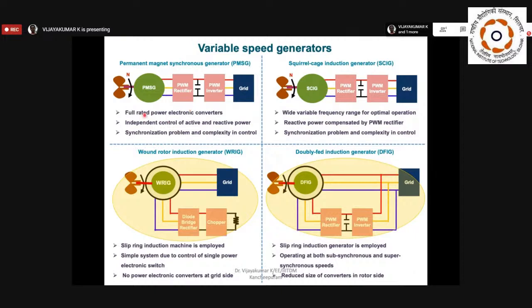So that's what I'm saying is a full rated power electronic converter. The converter ratings are equal to the machine rating. So in this case also, the converter ratings are equal to the machine rating, right? With these generators, it's possible to control the active and reactive power, because this converter can be used to maintain the voltage at the DC capacitors, and this PWM converter can take care of the speed control of the turbine to implement maximum power point tracking.